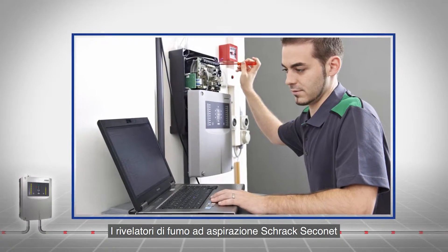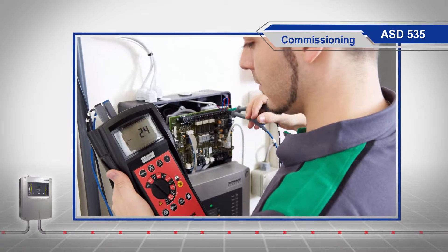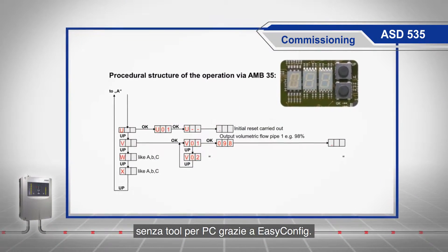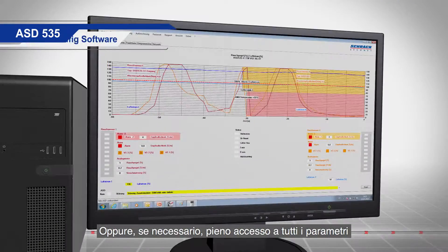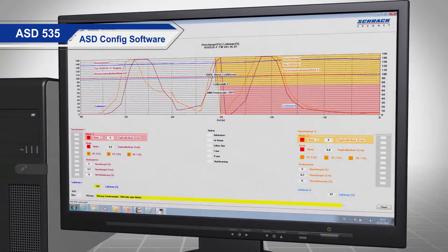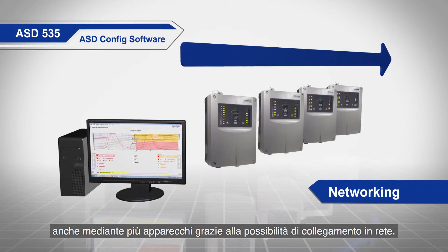Schrack Seconet aspirating smoke detectors are also the first choice for installers. Simple commissioning without a PC tool is possible thanks to EasyConfig. Alternatively, full access to all parameters can be granted using the ASD config software, and thanks to networking possibilities, this can also be done on multiple devices.